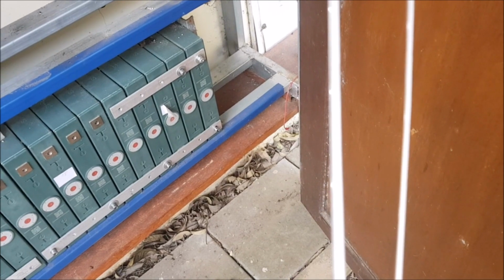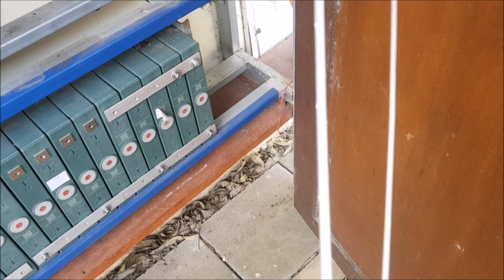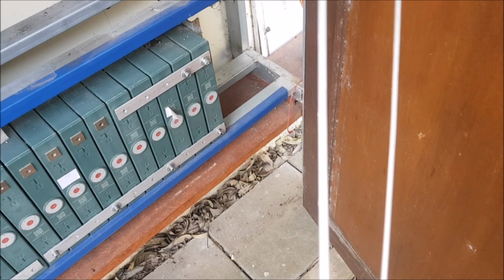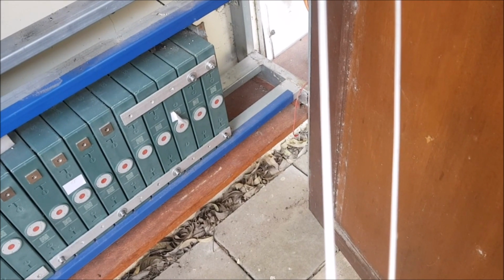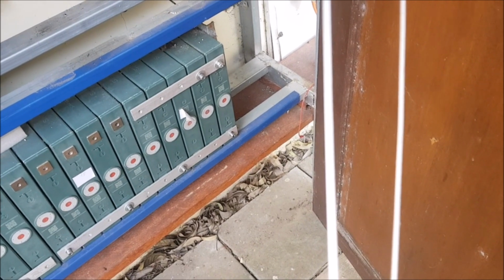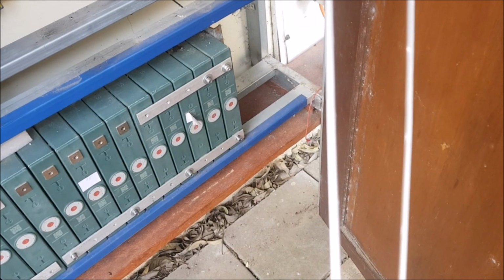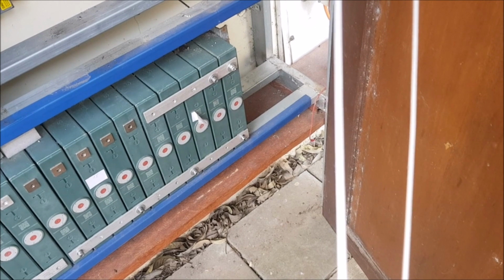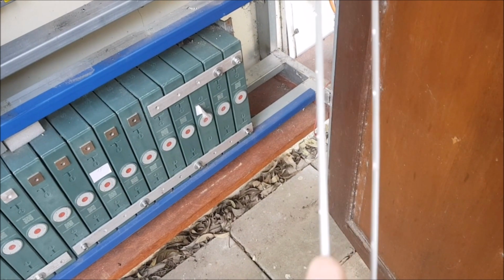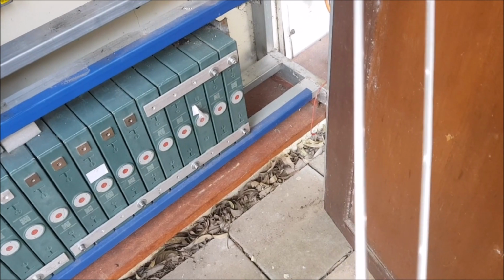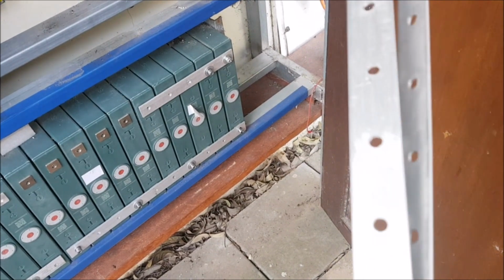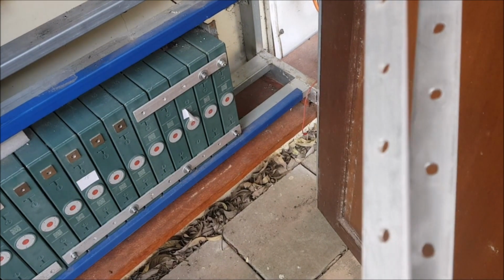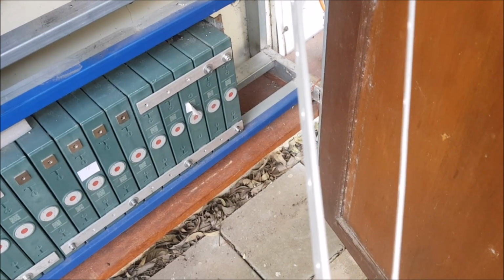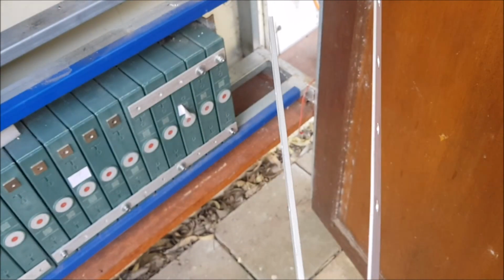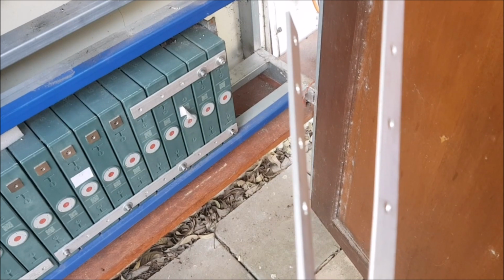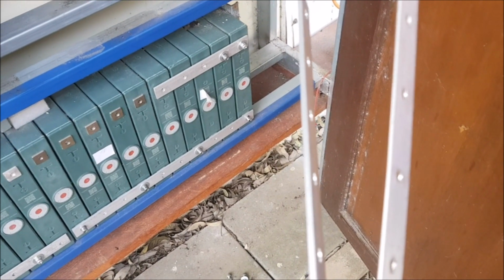Before replacing the last bus bar, let me show you the difference. The right bus bar you see here was actually never supposed to go on the system - it was just a mix-up because of imperial and metric measurements used here in Thailand, and I wasn't aware of this. So now this bus bar is going in here - it's 3 millimeter aluminium by 2.5 centimeters. The thin bus bar was still no problem at 60 amps; of course a bus bar like this can still carry a lot of current, but this will be fixed now going forward.